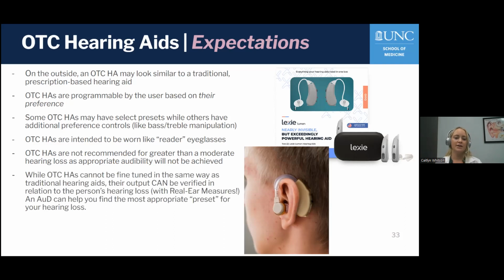And while OTC hearing aids can't be fine-tuned in the same way as traditional hearing aids, in other words, they can't be tuned frequency by frequency based on the amount of hearing loss at each frequency, their output can be verified in relation to a person's hearing loss. So, like I mentioned before, we can do real ear measures on anything. And in a consultation with an audiologist, if you have an OTC hearing aid, we can help you find the most appropriate preset for your hearing loss.